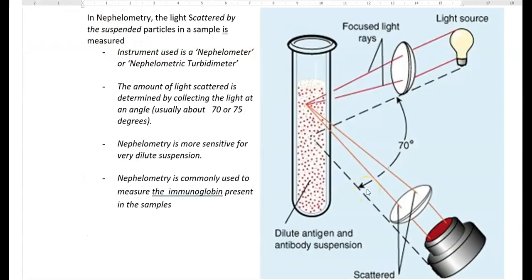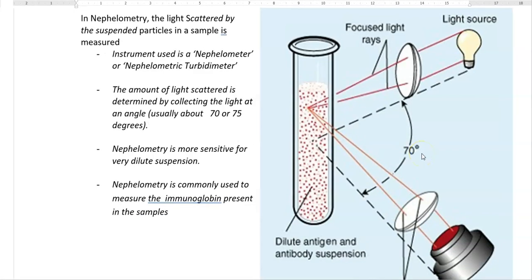Next, we look at points related to nephelometry. It measures the intensity of scattered light. In nephelometry, the light scattered by suspended particles in a sample is measured. The instrument used for this purpose is a nephelometer or nephelometric turbidimeter. The line diagram of that instrument is shown on the right hand side, where you can see the amount of light scattered by suspended particles is collected at an angle of 70 to 75 degrees. Nephelometry is more sensitive when using dilute suspension for measurement. Nephelometry is commonly used to measure immunoglobulin levels present in samples.